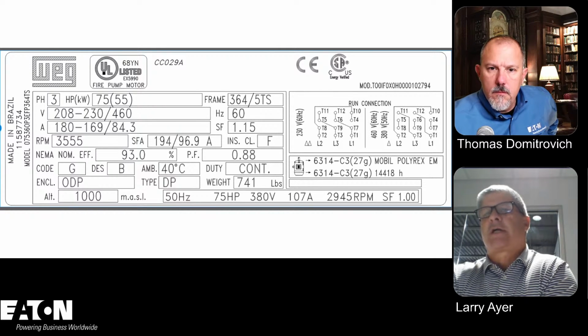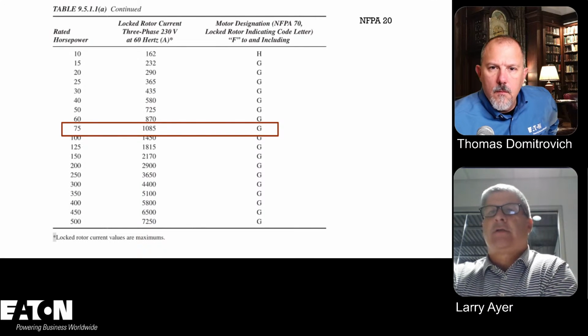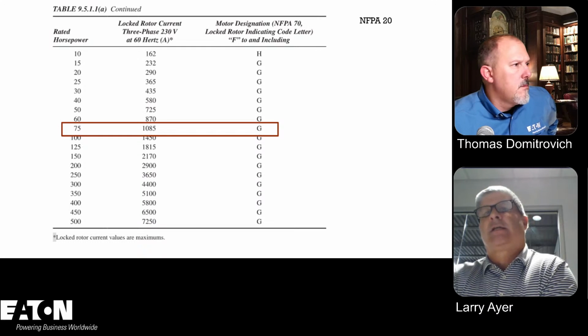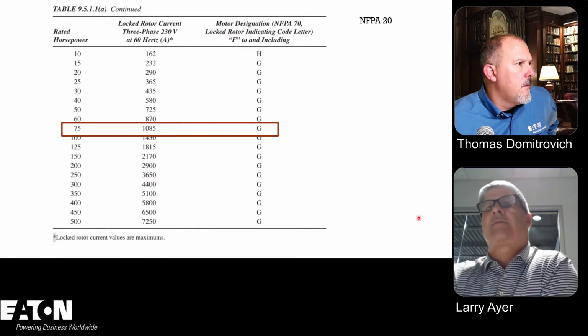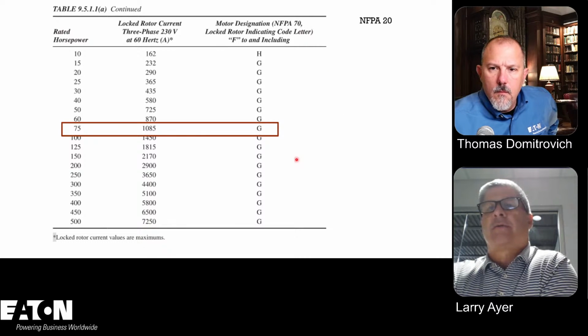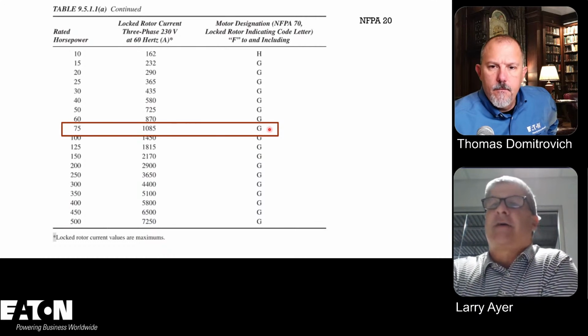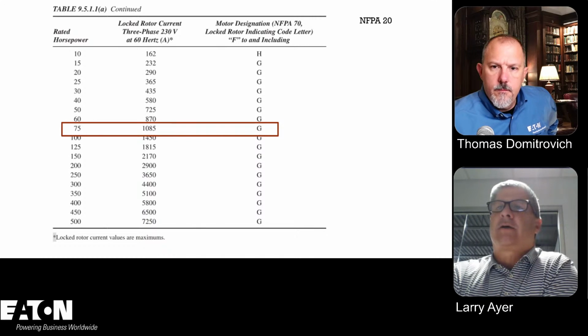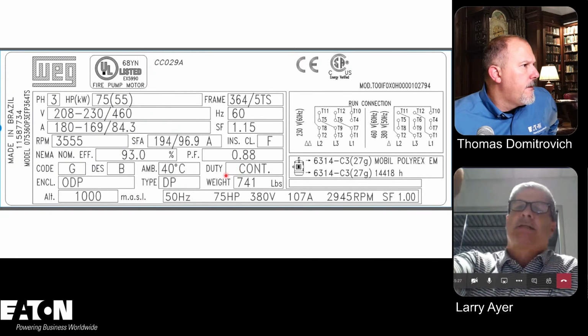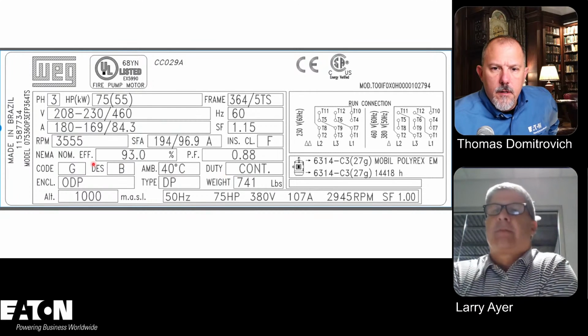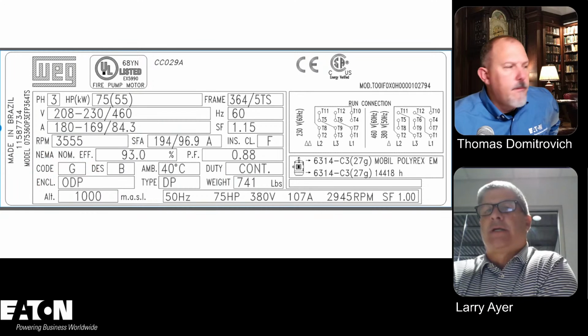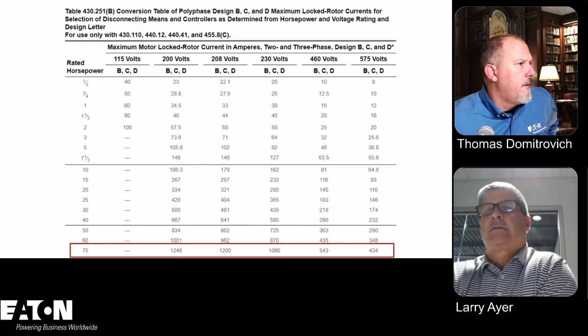But what you should do is look at the design code there, B, and then go to a table to make sure you size your overcurrent protection accordingly. This is a table listed in Table 9.5.1.1 out of NFPA 20. You would go down to the 75 horsepower motor, and this tells you the short circuit current; my locked rotor current is 1085. Now that is with a code G. Go back to that slide. I said B, but that said code G. So, code G. There it is. I said B inadvertently. Now go to the next one.